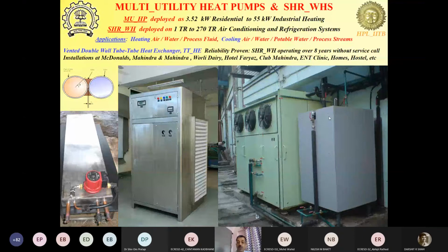This was generating free hot water for sanitation, as well as potable chilled water. And this potable chilled water was then used for dispensing as Coke or chilled water for drinking and other beverages. So instead of cooling the carbonated water from 30 or 32 degrees all the way down to 7 degrees in the countertop beverage dispensing unit, in this case the water was pre-cooled from 32 degrees to 15 or 12 degrees. And then that 15 or 12 degree water was further cooled down to 7 degrees in the countertop unit.